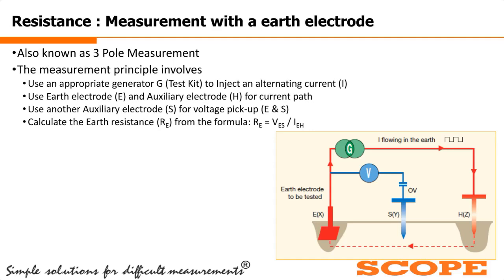So by using the formula RE equals V divided by I, where V is the voltage difference between E and S and I is the current we are injecting, we calculate the earth resistance with the help of the three-pole measurement method.